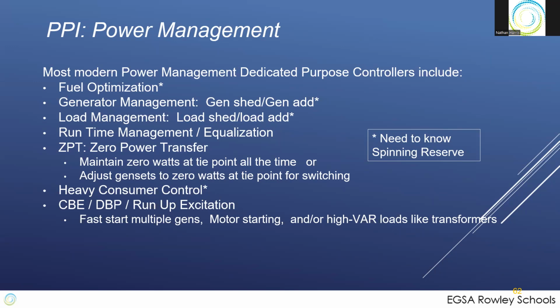Runtime management, it used to be runtime equalization. We tried to run our generators in our parallel power island with about the same number of hours in order to keep the wear and tear equal on the machines. Well, the problem we run into is a year down the road, they're all ready for maintenance at the same time, and I have to shut them all down to maintain them. We've got to shut our bus down. So let's rethink this a little bit. We're going to intentionally run some machines more than others so that when it comes time to do maintenance, we can take generator 1 offline and maintain him and run off 2, 3, 4, and 5. And then we put 1 back on and maintain 2 and run off 1, 3, 4, and 5. You get the idea. So it's managing the runtime hours so that they're not all due at the same time.